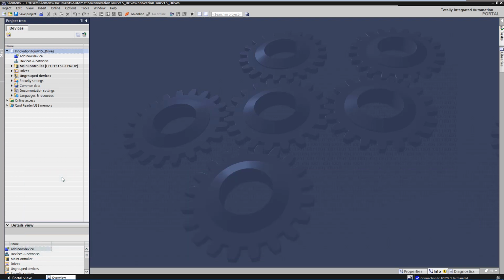In this video, we want to show you how easy and fast the safety integrated function of SINAMICS can be approved. Why do you need acceptance tests? The EG Machinery Directive and DIN EN ISO 13849-1 require the testing of safety relevant functions and machine parts after commissioning as part of the so-called acceptance test.